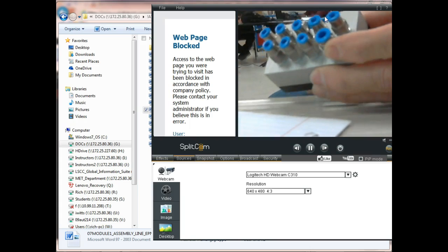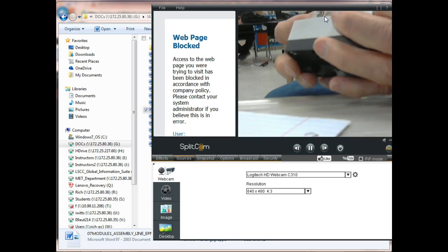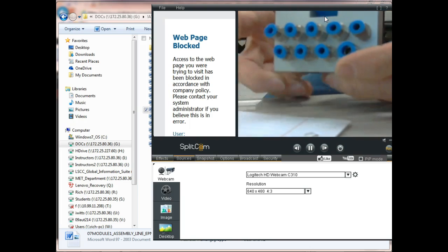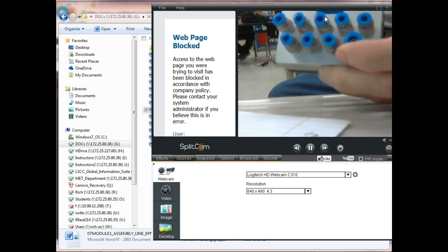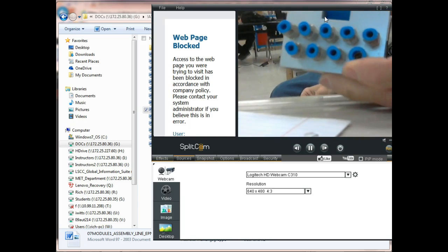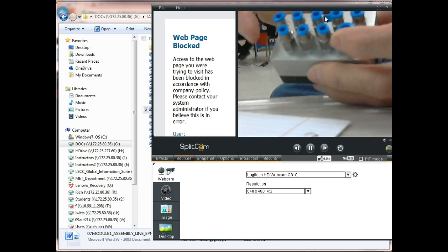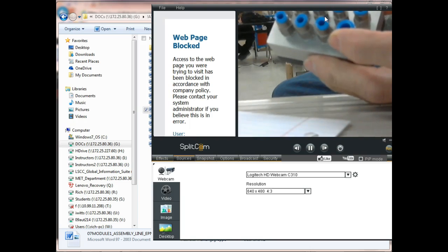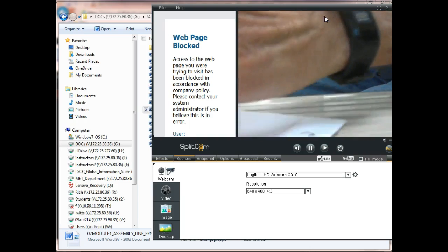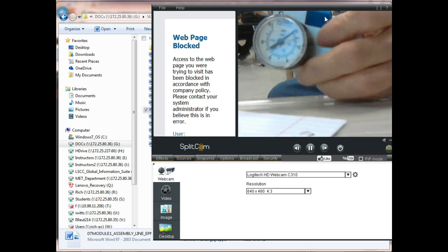By the way, the way these quick disconnects work, if you don't have a tube in them, then they block the air. So what we can do with this manifold is have one pressure coming in, and then output this many pressures to different devices out in our system. Are we okay there?